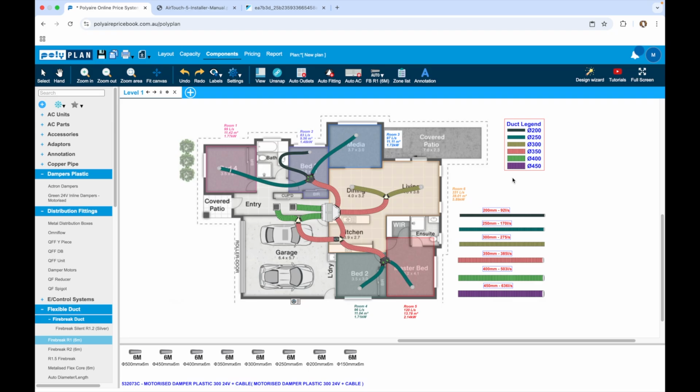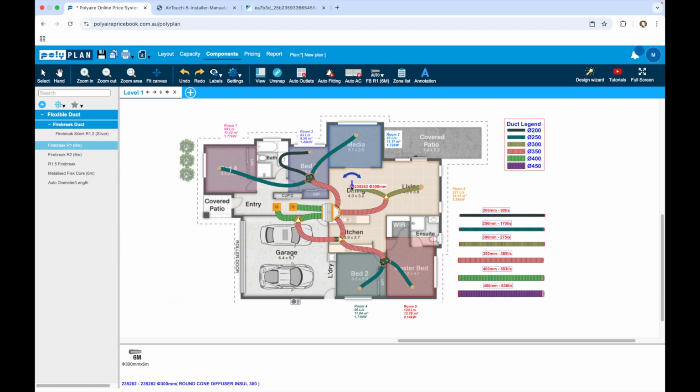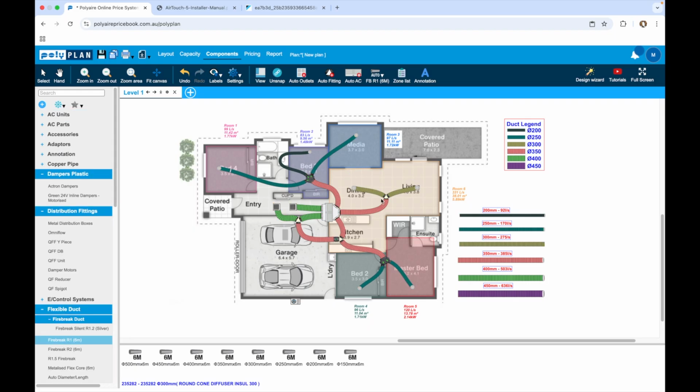If somebody is telling you that they're putting constant zones in, you need to look elsewhere, because it's an indicator to me, a red flag, that someone doesn't understand what they're doing or talking about. The only advantage is there's no mechanical component here to fail, but you know, they're everywhere else, and it's a bit of a dumb argument.